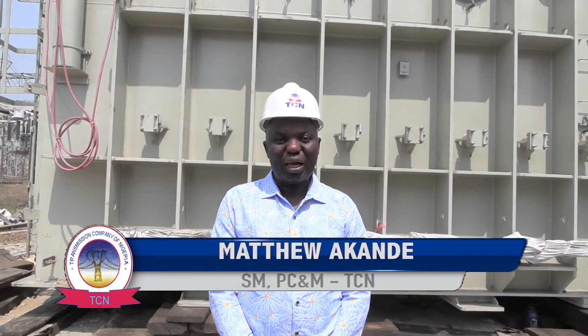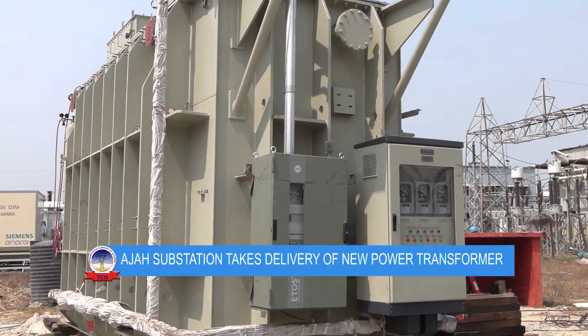The transformer just came in the day before yesterday, and it's one of the SLA projects that is ongoing at Ajah. The rating of that transformer is 1 by 100 MVA, 132 by 33 kV. Once the new 100 MVA transformer is energized, it will increase the wheeling capacity of the power transmission substation from 280 megawatts to 360 megawatts at the 132/33 kV level of the Ajah transmission substation.